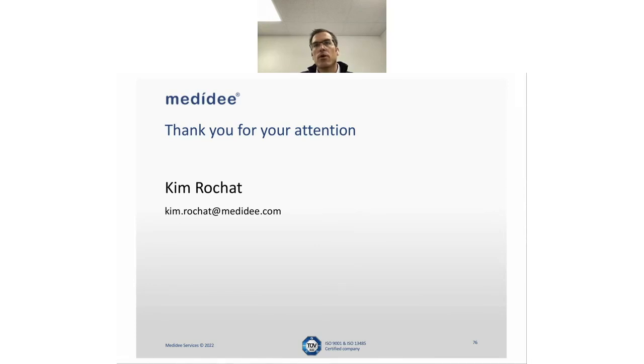Question from Bernard, with regard to property right, how much of the software coding has to be disclosed? Well, you need to consider one thing. Within the medical device regulation, or let's say within the medical device validation process, there is no secret with regard to your notified body. So if you're interacting with a notified body, the notified body can ask you any question and you have to answer. Now the notified body is also under confidential agreement. I mean, by definition, that's part of their accreditation requirement that they have to handle confidentiality. Competent authority, when they challenge you, they also have the right to ask you whatever question they like. And you have to respond, so you cannot hide anything. So at the end of the day, if the competent authority is asking you to share the code, you have to share the code. But be aware that it's unlikely to happen.